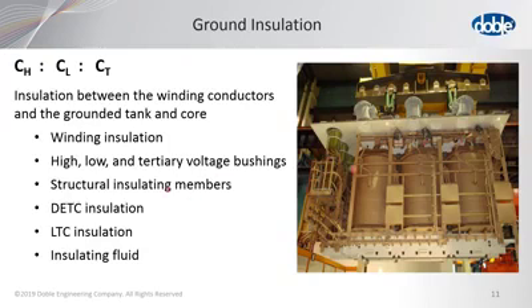Structural insulating members. Now this is something that people don't often think about, but these structural members are energized during the test. It makes a difference which winding, of course, you're energizing. In this case, the high voltage winding is here. Any path to ground is stressed. If there was tracking along that insulating member, it could be identified with the test.